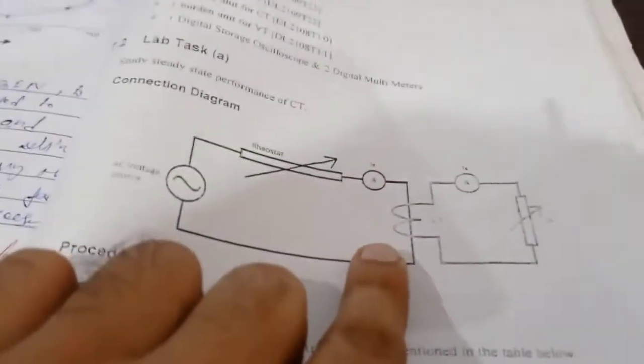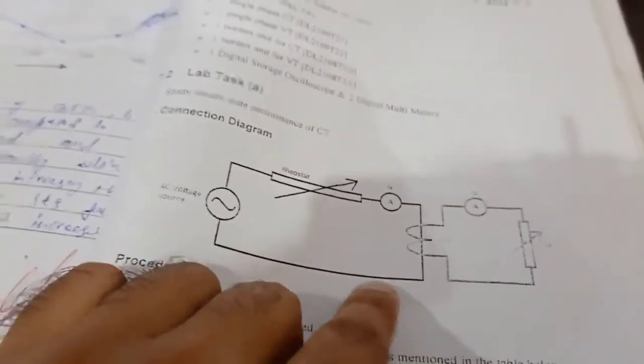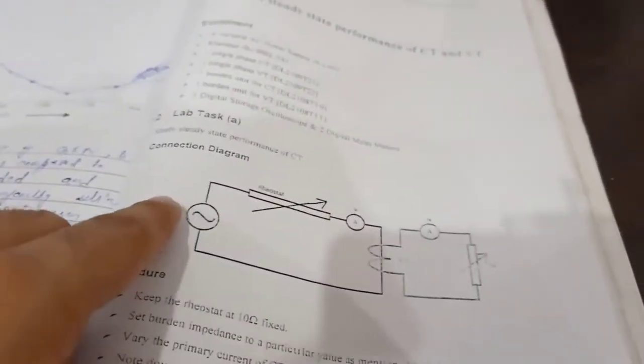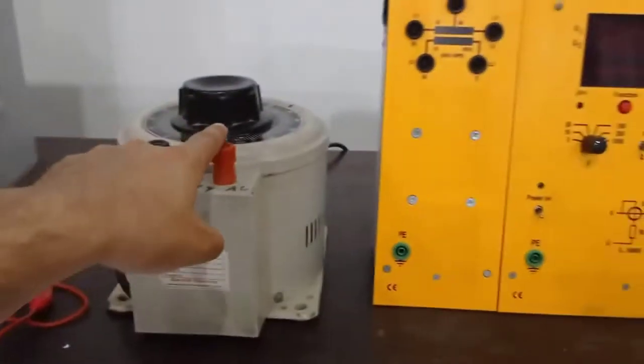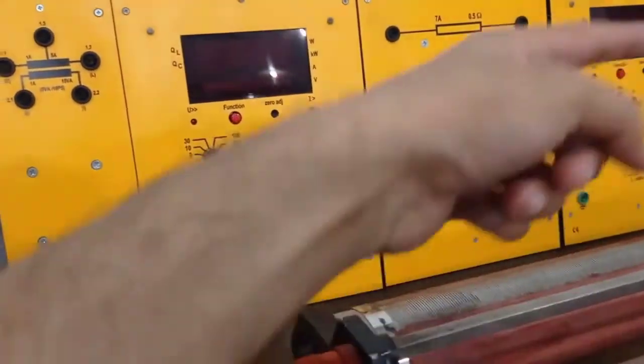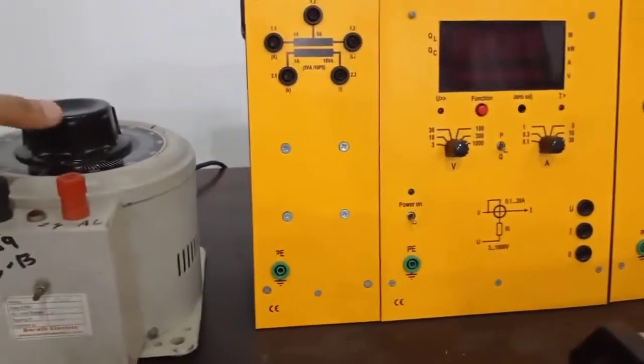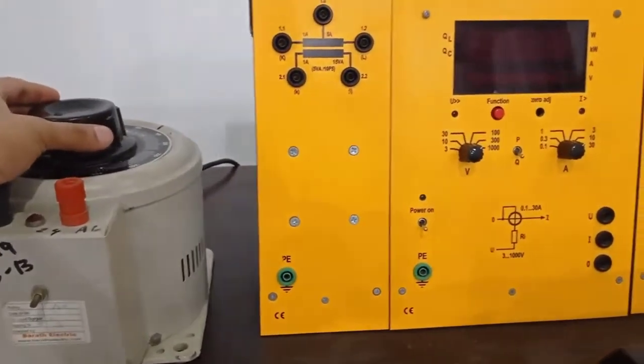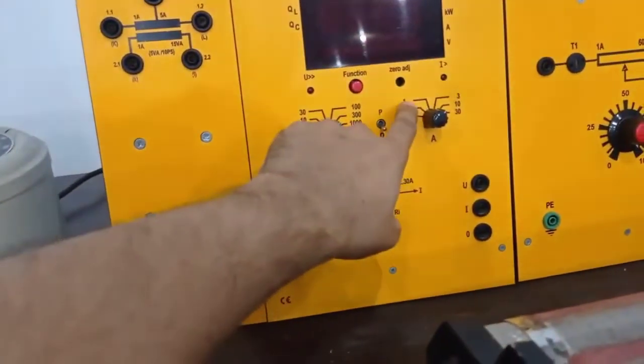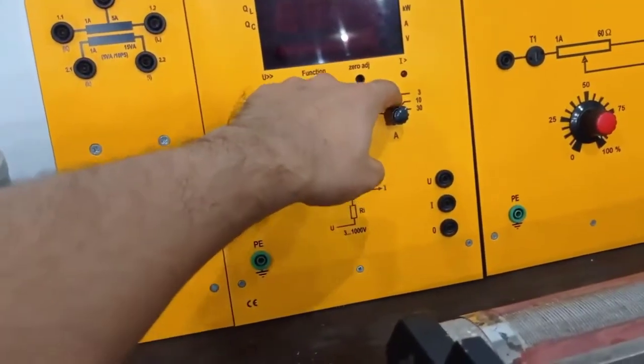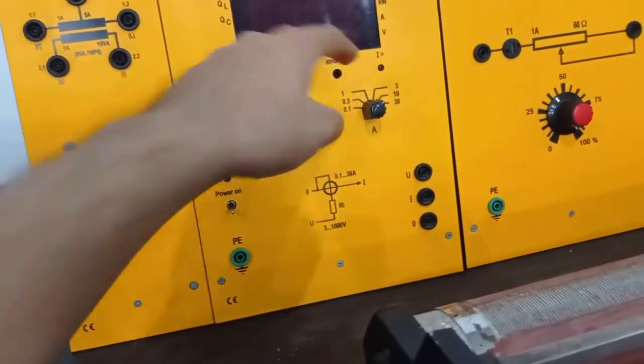Next is the primary winding, and all these components are connected in series in a single loop. So make sure that the source, the primary of the CT, the ammeter and the rheostat are connected in a closed loop, and you can adjust the value of current by controlling the voltage here. Make sure that the selector switch on this ammeter is set to the 10 ampere range.